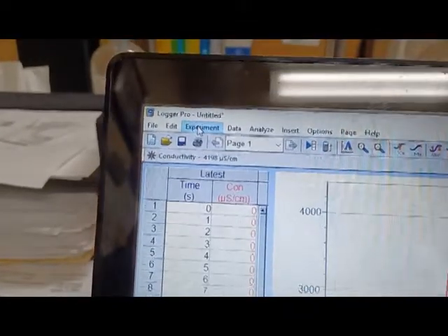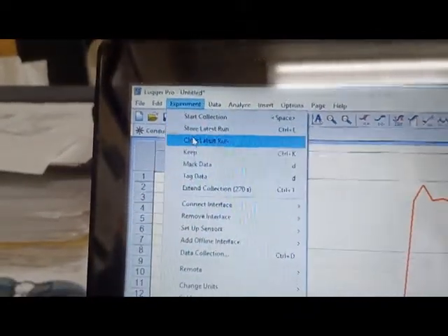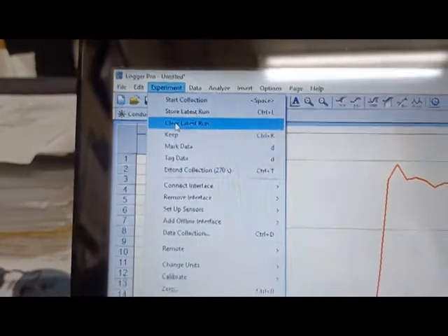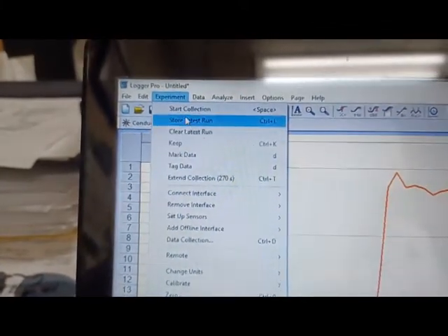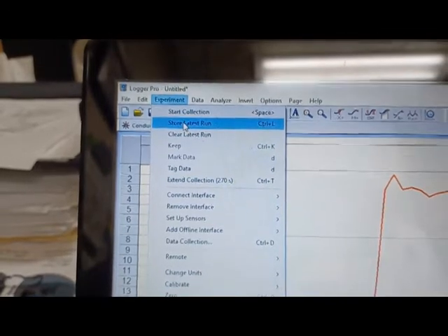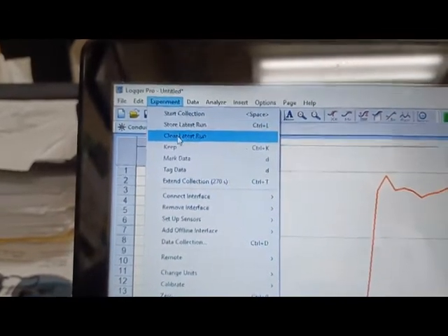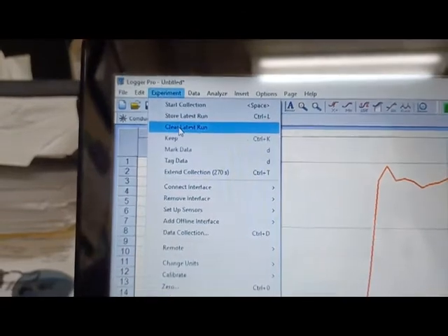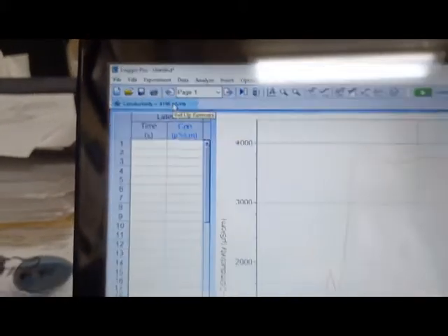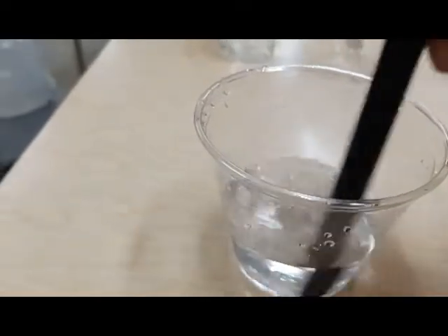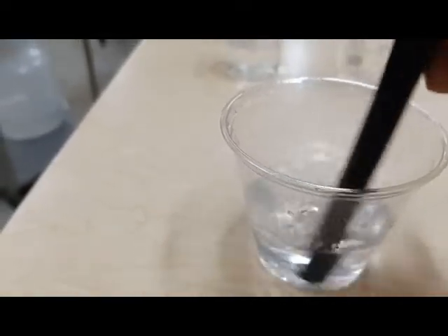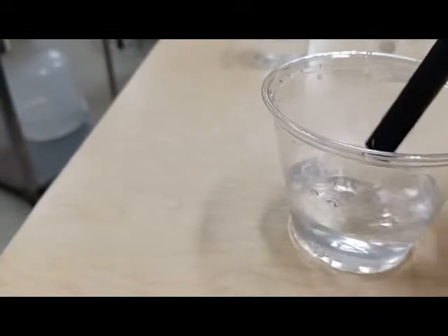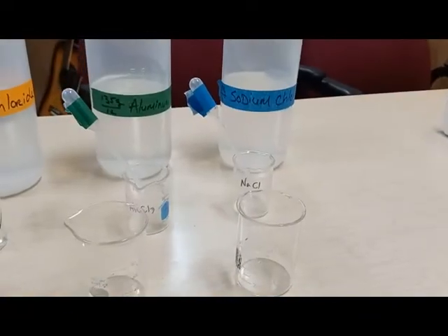Now, if you made a mistake and want to start over again, you would press clear run and start over again. But you could also save that run and compare it to the next solution. So you would just click store run for this one, not clear, because clear will clear and you start over again. So you want to hit store run and it keeps it on the graph, and then start your next solution. But first you got to clean the probe using the tap water in your plastic cup. Once that's truly clean, you can start with the other solutions.